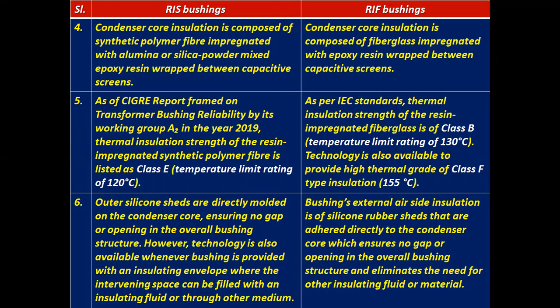As per the CIGRE report framed on transformer bushing reliability by its working group A2 in the year 2019, the thermal insulation strength of the resin impregnated synthetic polymer fiber is listed as class E insulation, that is a temperature limit rating of 120 degrees centigrade.